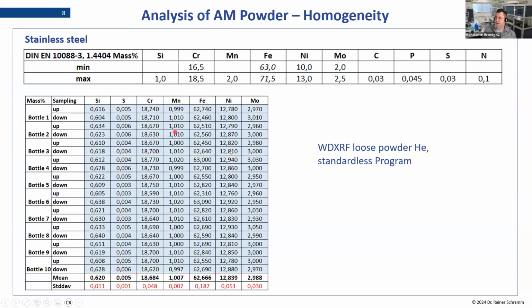So in this one, we can see we made the homogeneity test, basically taking different bottles from the same charge, and we just looked at the measurements. We used standardless software for these measurements, and this was one of our wavelength dispersive XRF machines under helium. So we basically filled it in a cup and measured it standardless. And as you can see, the homogeneity of the powder is really good.